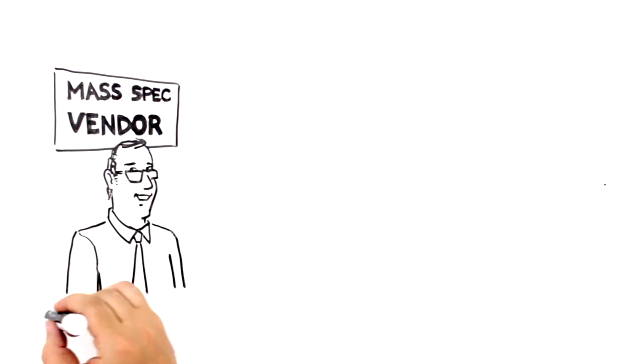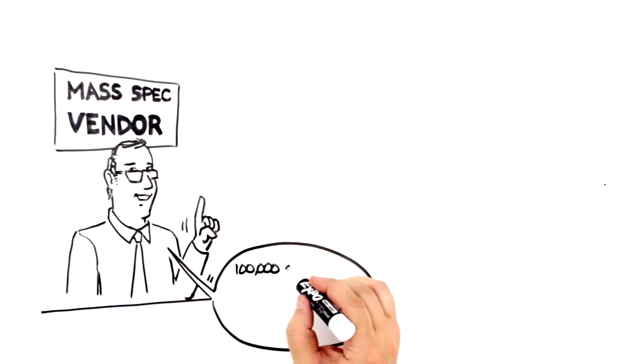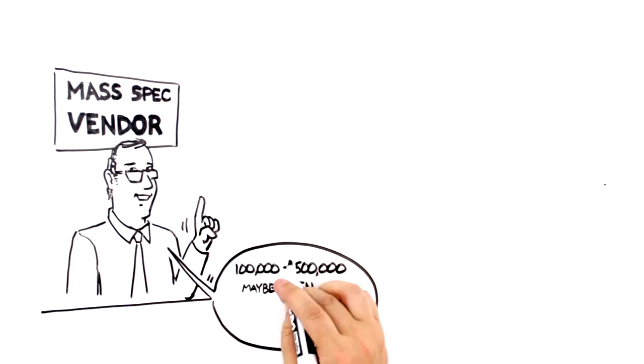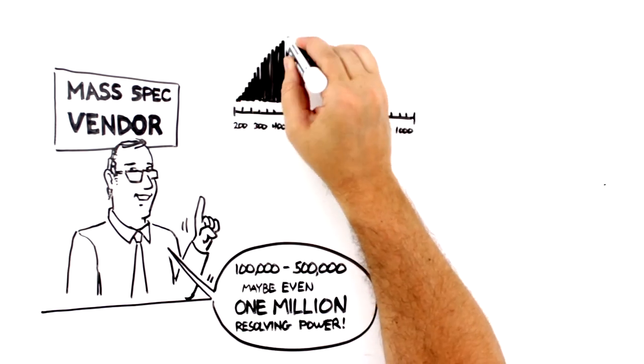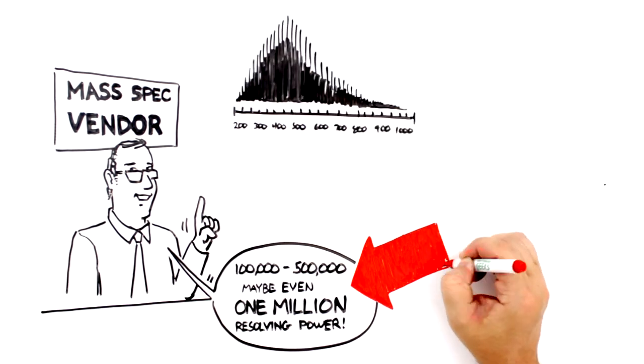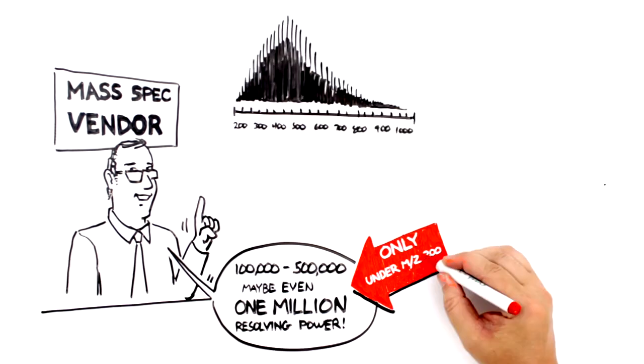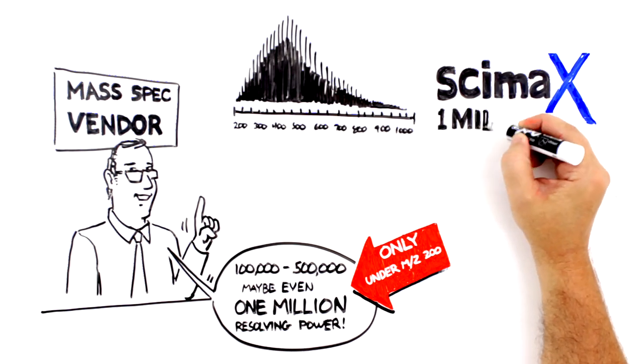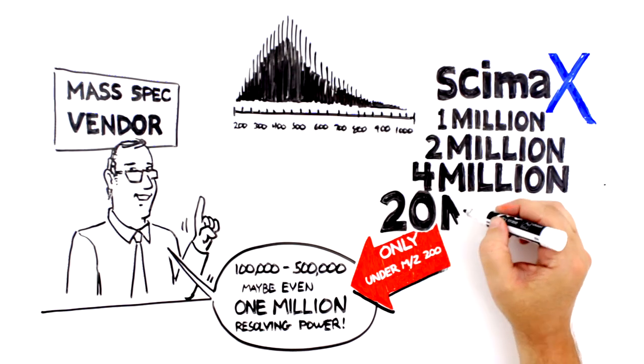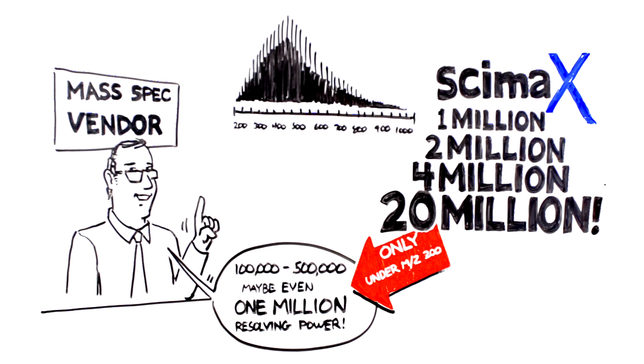Look, other mass spec vendors might claim 100,000 or 500,000 or maybe even 1 million resolving power, but that is only applicable to a small part of the mass range, typically under mass to charge 200. ScimaX gives you a million, or 2 million, or 4 or 20 across a wide mass range. You have the flexibility to choose what resolving power you need based on the problem at hand.